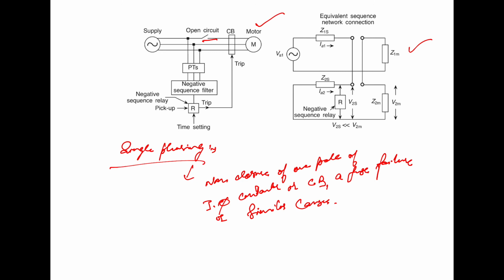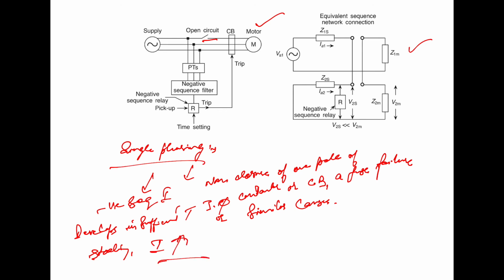Single phasing causes negative sequence current to flow. The motor has limited ability to carry the negative sequence current because of thermal limitations. Single phasing also causes the motor to develop insufficient torque, leading to stalling. And when it is stalling, it draws excessive current and leads to burnout.